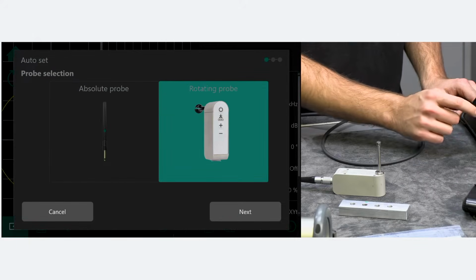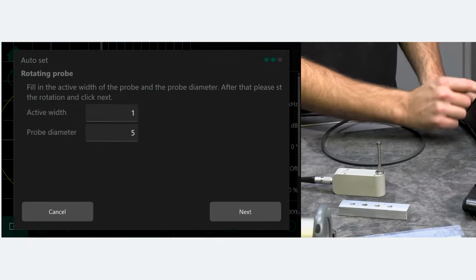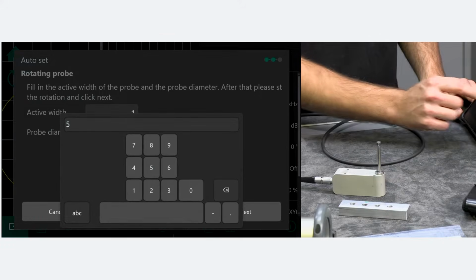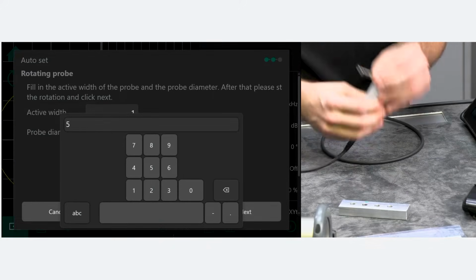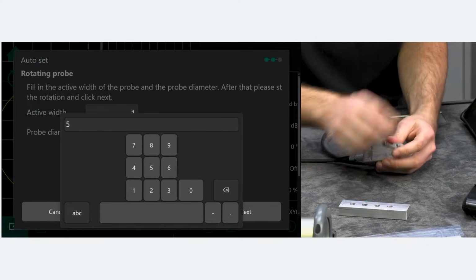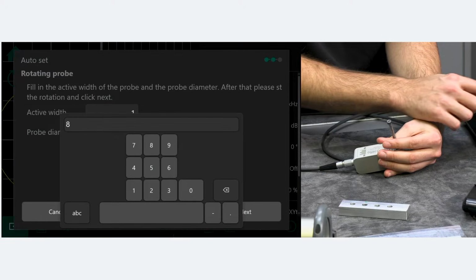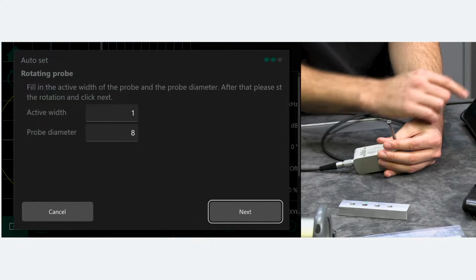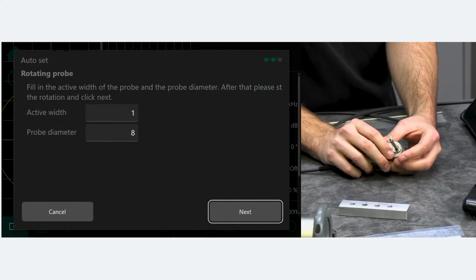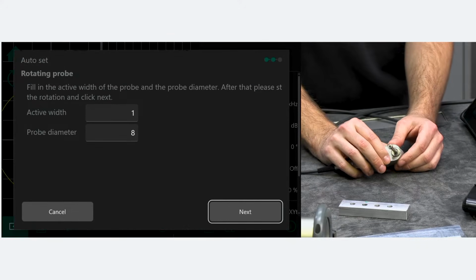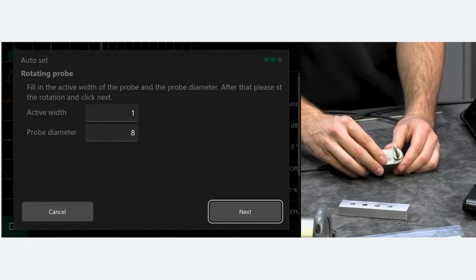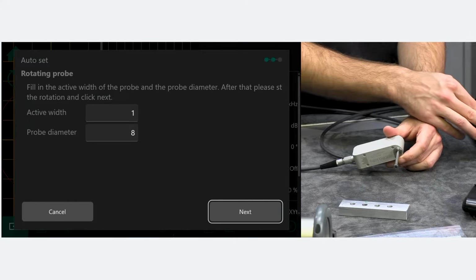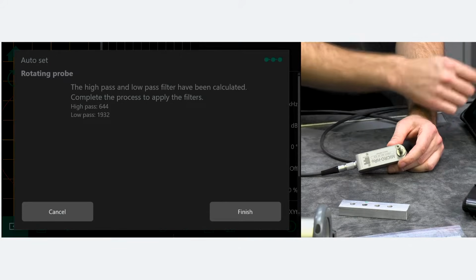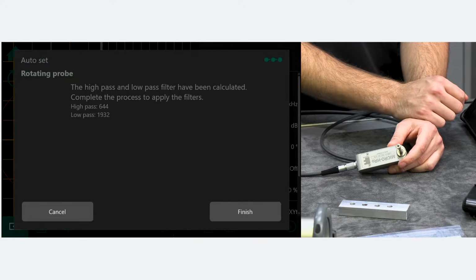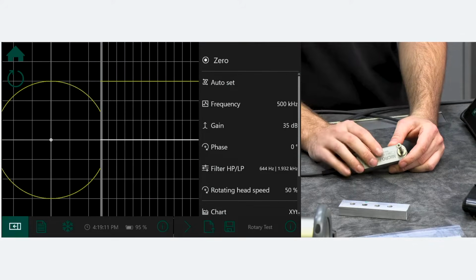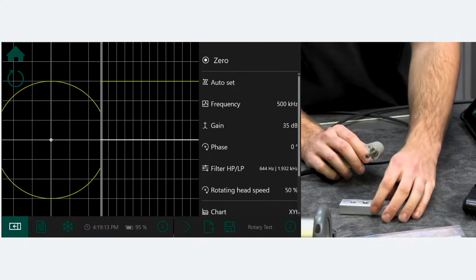Okay, and now we have the possibility to go with auto set. Choose rotating probe. And there we have a probe diameter. On the probe it's written that we have a probe diameter of 8 millimeters. And it says, after that, please start rotation and click next. So we start the rotation of the rotating probe and click next. And it automatically calculated the filters, and we can start with testing.